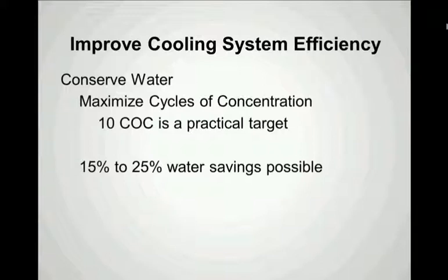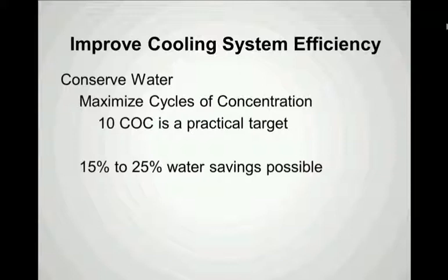That is a point that needs to be discussed with your water treatment vendor or consultant to make sure you are operating at maximum cycles. If you are able to achieve that 10-cycle target, you can expect a 15 to 25 percent water savings over the traditional cycles of concentration, which tend to be around 3 to 4 — significant gains that can be made on water consumption by focusing on cycles of concentration.